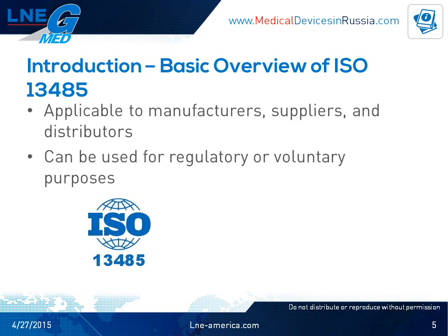ISO 13485 is applicable not only to medical device manufacturers, but also suppliers of products and services to medical device manufacturers, including distributors. Likewise, many times sterilizers also have ISO 13485 certificates for sterilization services. Now, ISO 13485 is a voluntary standard for the EU, so it's a harmonized standard, EN ISO 13485-2012, but it may be required by other medical device regulatory authorities. For example, ISO 13485-2003 is required to market devices in Canada.